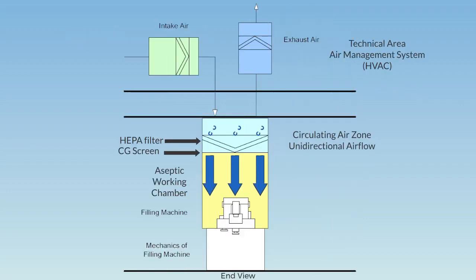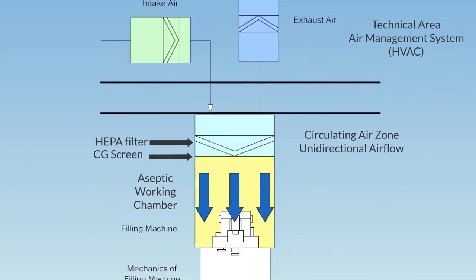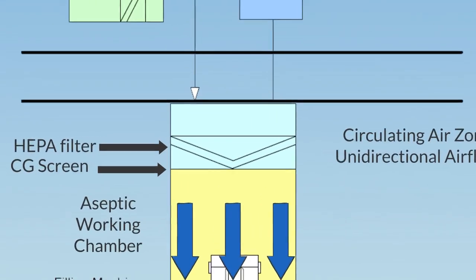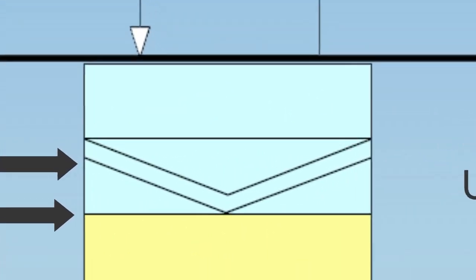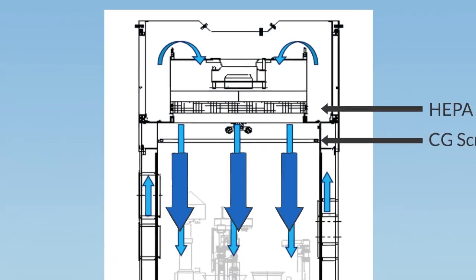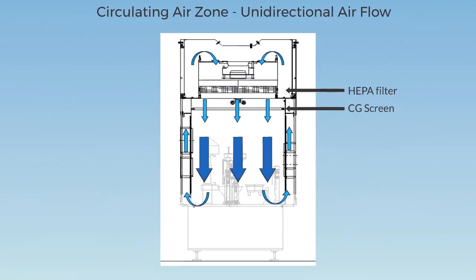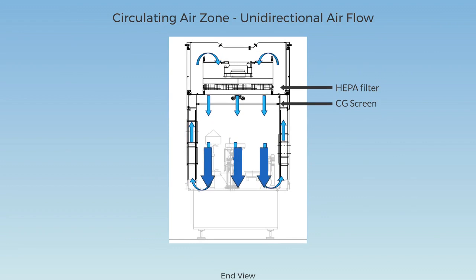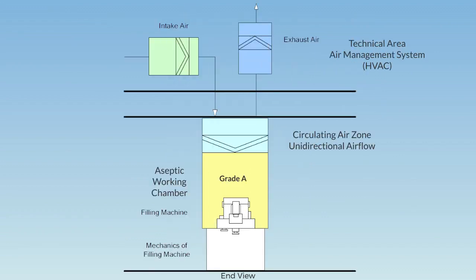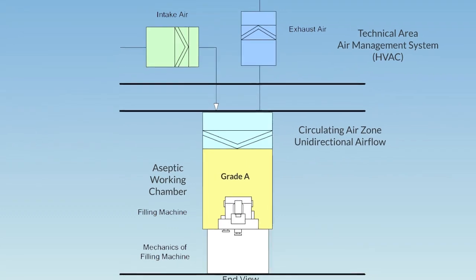The unidirectional airflow within the working chamber of the isolator is created by flowing fan-filtered air through HEPA filters and CG screen that convert turbulent air to laminar air in a vertical direction down to the process machine, over the product and away from the base plate to the air return ducts. The aseptic working chamber of the isolator is the critical area.